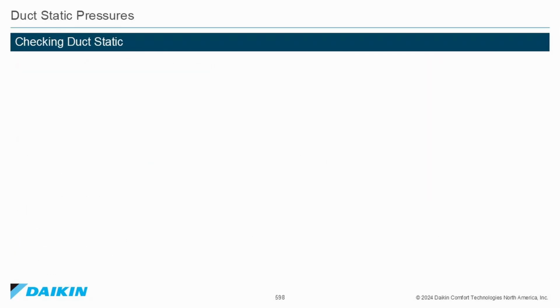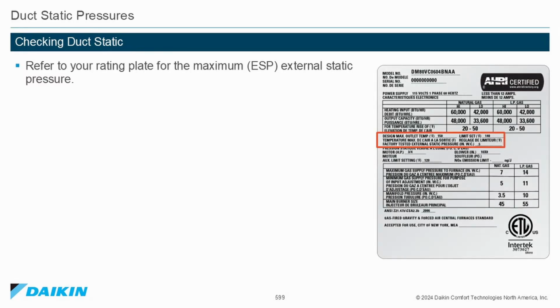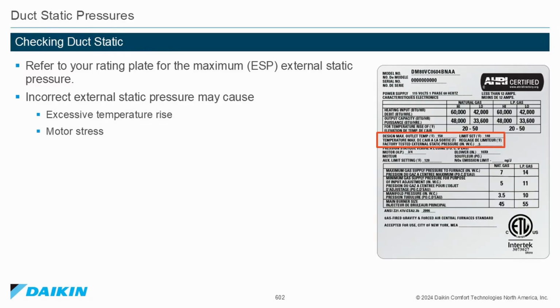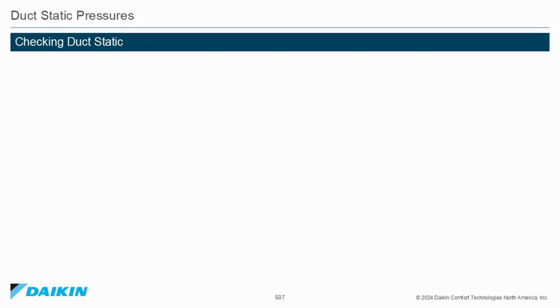Duct static pressures. Checking duct static. Refer to your rating plate for the maximum external static pressure, or ESP. Incorrect external static pressure may cause excessive temperature rise, motor stress, duct stress, reduced performance, unwanted condensation, etc.